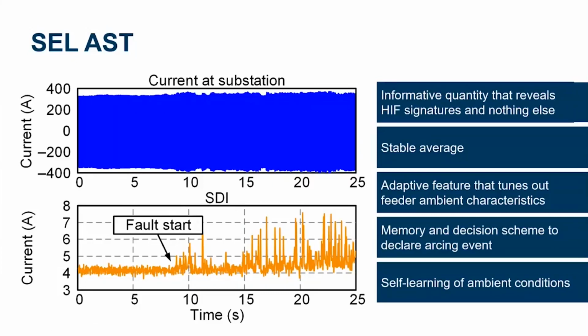However, if we look at this signature from our sum of difference currents, we can clearly see the fault signature. We can see something is happening here. We have our baseline here, and now we start to see some activity. We can clearly see that there is arcing on the system, and we can use this information to assert that there's a high impedance fault on the power distribution system.